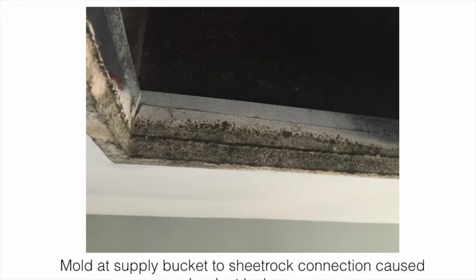This is a picture of the supply bucket to sheetrock connection, and in humid climate zones the hot humid air is going to be drawn towards the cold surface, and when you have duct leakage at the sheetrock like this behind the grill, I mentioned earlier that the static pressure will build up behind the grill and force the air out. Well, while that air is being forced out, it's creating a cold surface where the humidity can really attract to it, and here's a perfect example of duct leakage causing mold in ductwork.